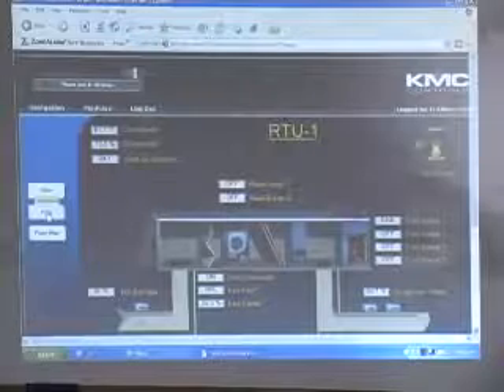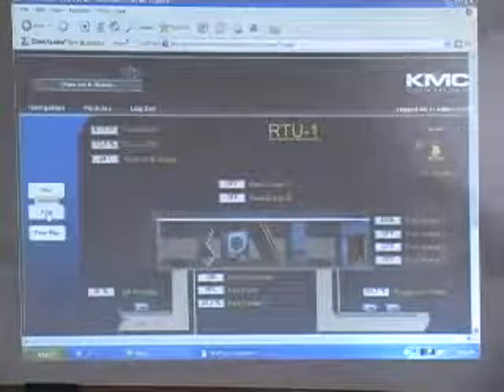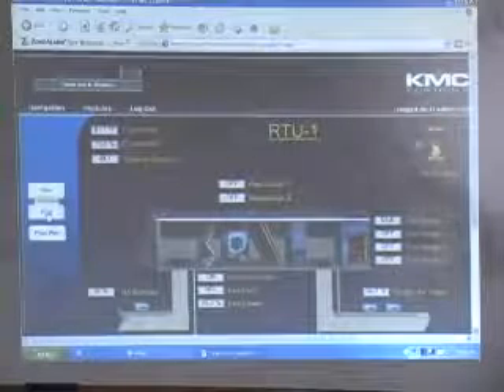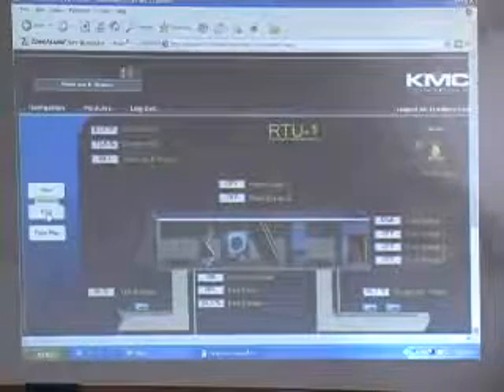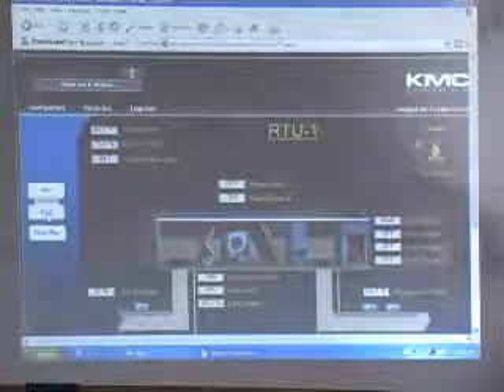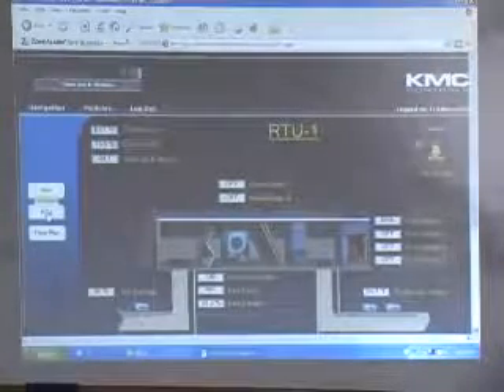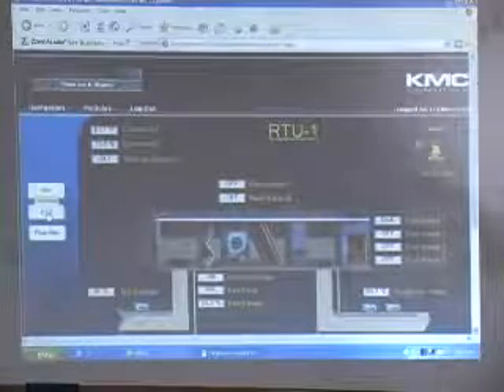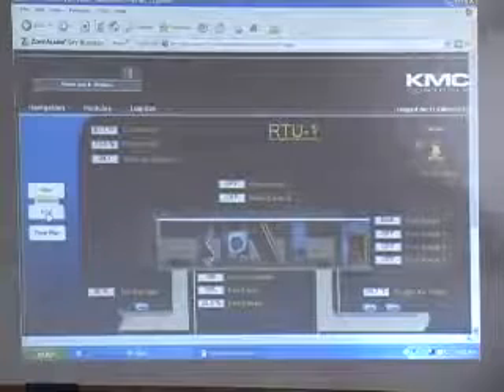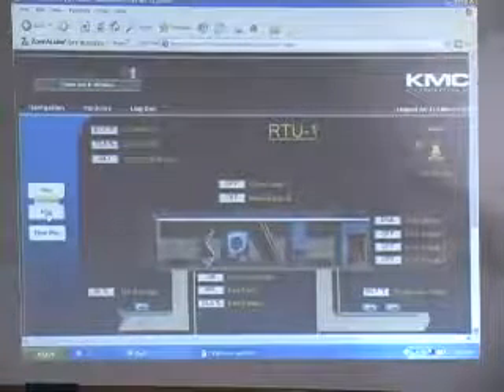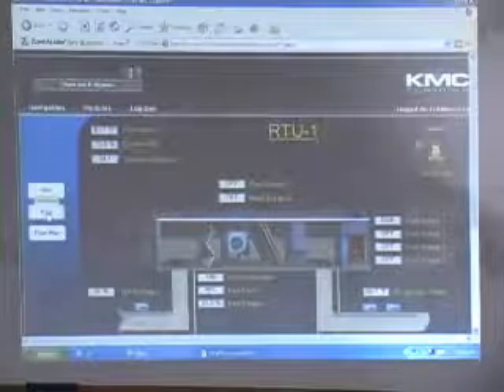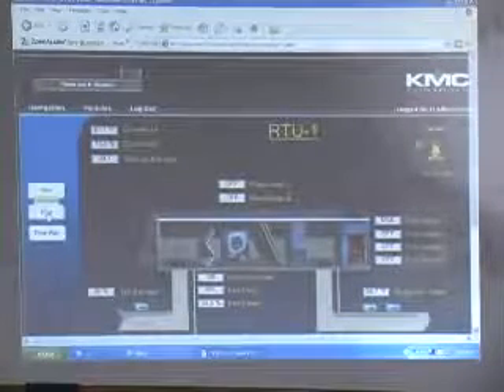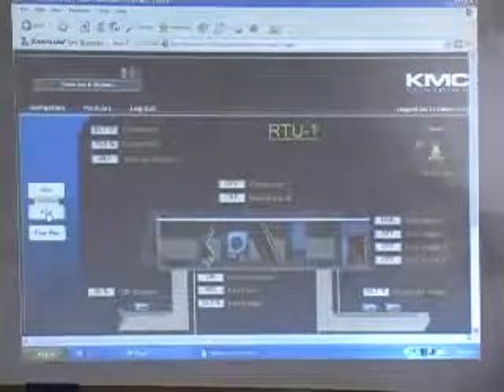I don't want to be on the solar anymore. This rooftop itself, I believe, is a Carrier rooftop with its own control system, and we have a KMC control system operating the building. So our building automation system is KMC, but the engineer specified BACnet as the protocol he wanted to adopt on this project. So the folks that provided the rooftop equipment had to make sure it was BACnet compliant. Our system is BACnet compliant, so we just mated the two and integrated them, and all this information from the rooftop is based on what Carrier made available for points.